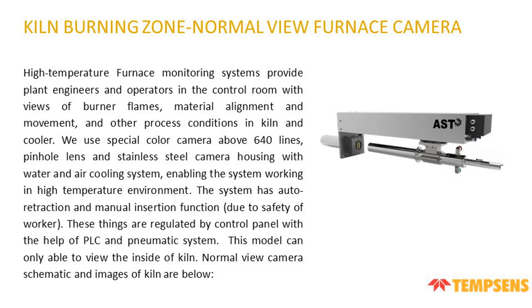The high temperature furnace monitoring system provides plant engineers and operators in the control room with a view of the burner, flame, and material alignment. It uses a special color camera above 640 lines, pinhole lenses and a stainless steel camera housing with water and air cooling system, enabling the system to work in a high temperature environment. The system has automatic retract and manual insertion functions. These are regulated by a control panel with the help of a PLC or PCB and a pneumatic system.